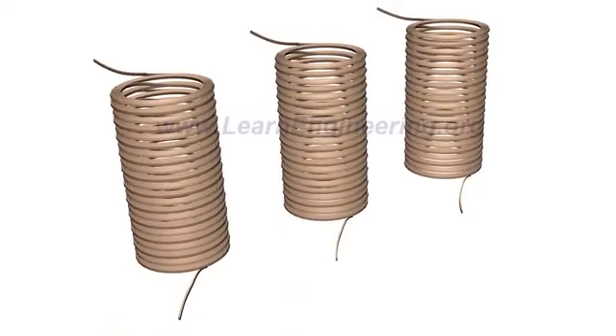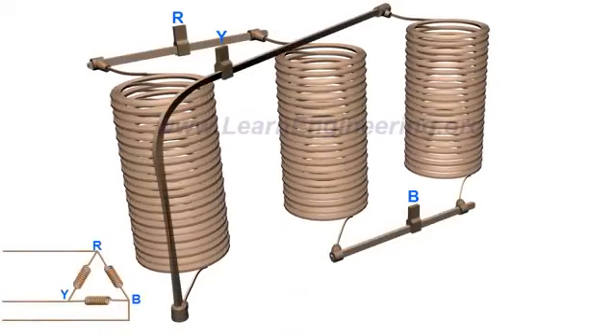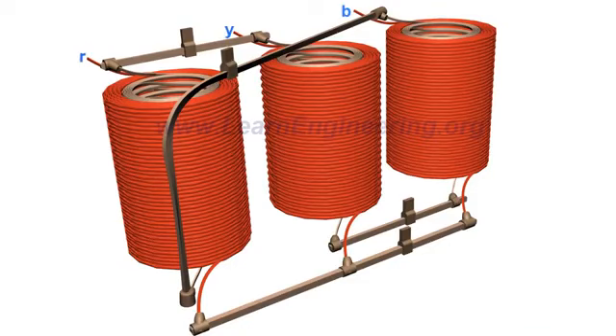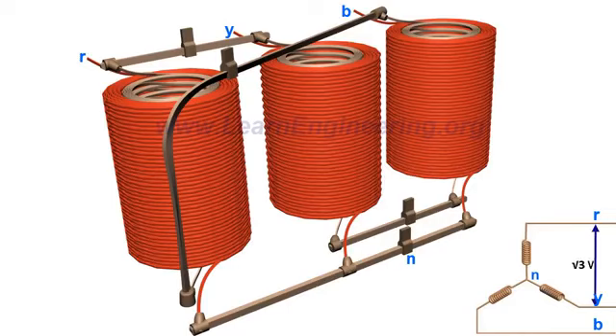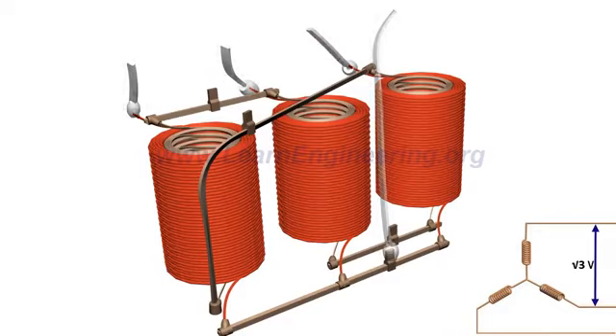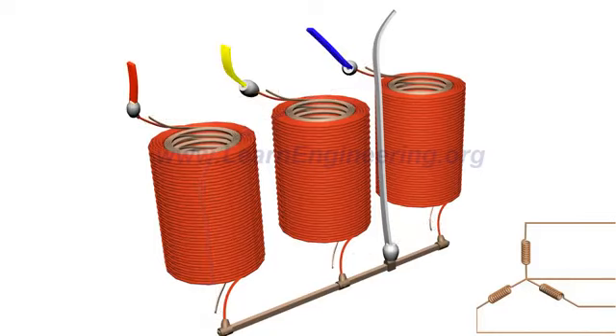The low-voltage windings are connected in a delta configuration, and the high-voltage windings are connected in a star configuration. Thus, the line voltage further rises to root three times at high-voltage side. This also means that, from a three-phase step-up transformer, we can draw four output wires: three-phase power wires, and one neutral.